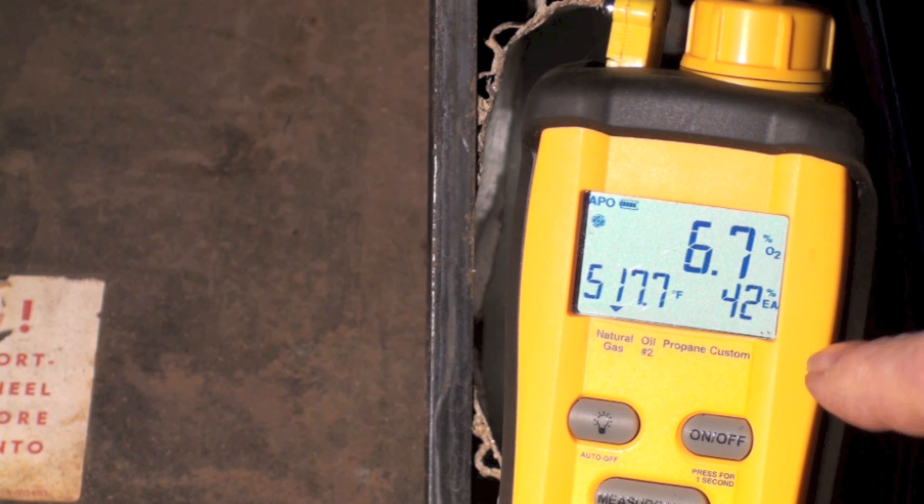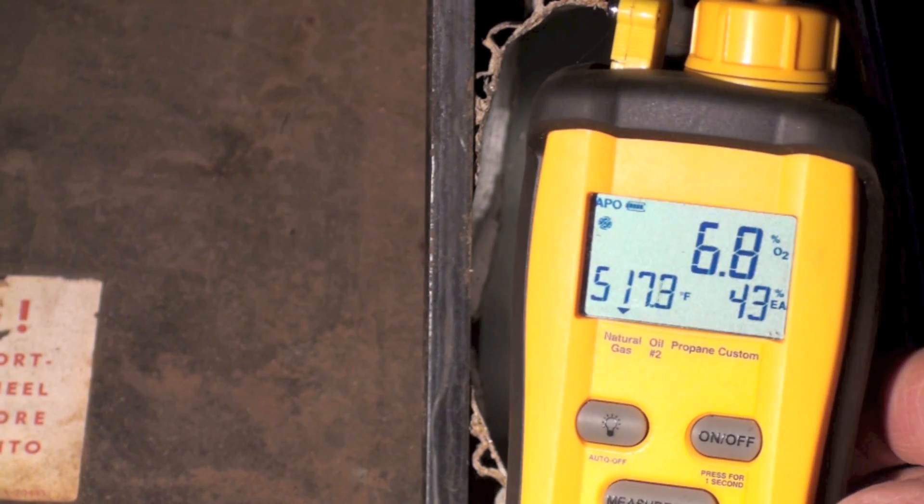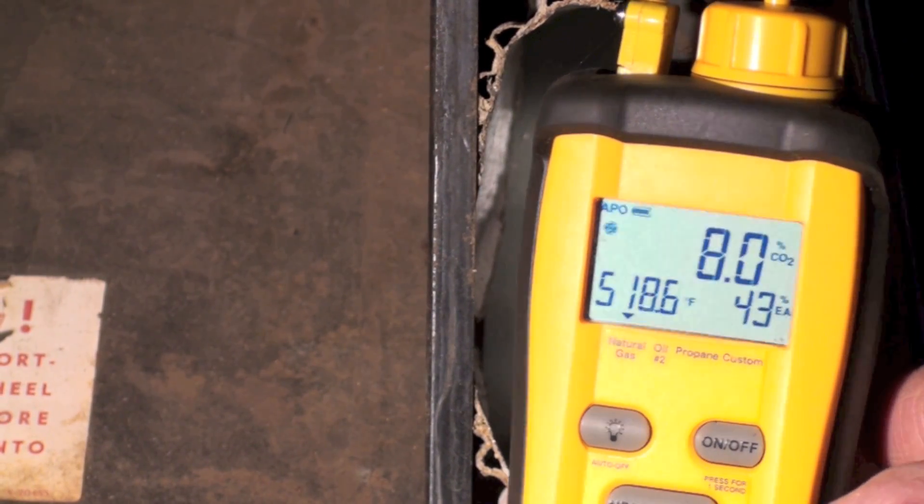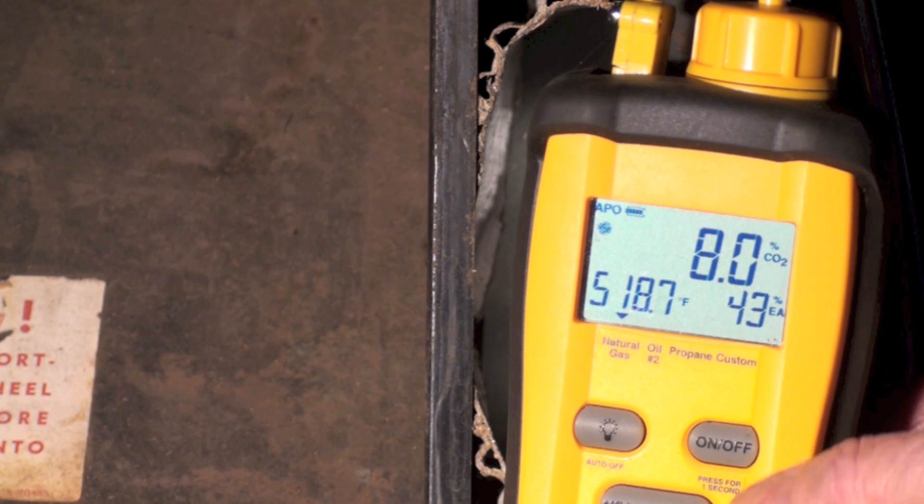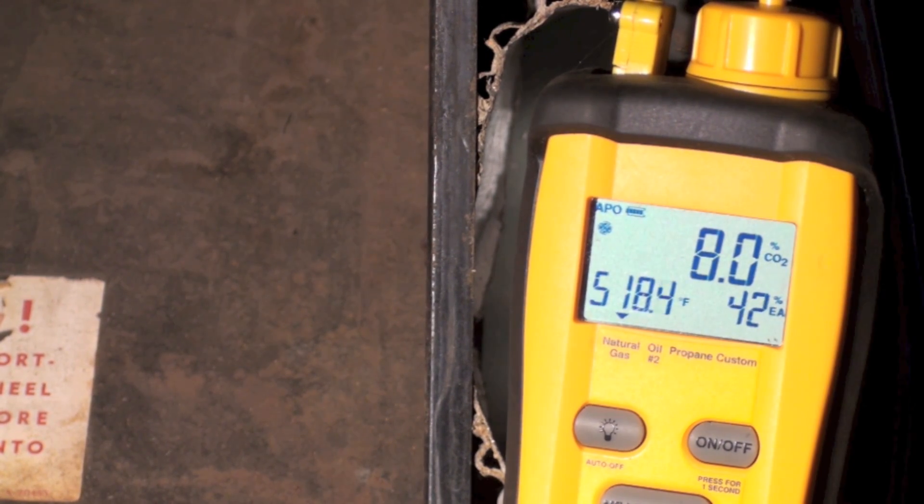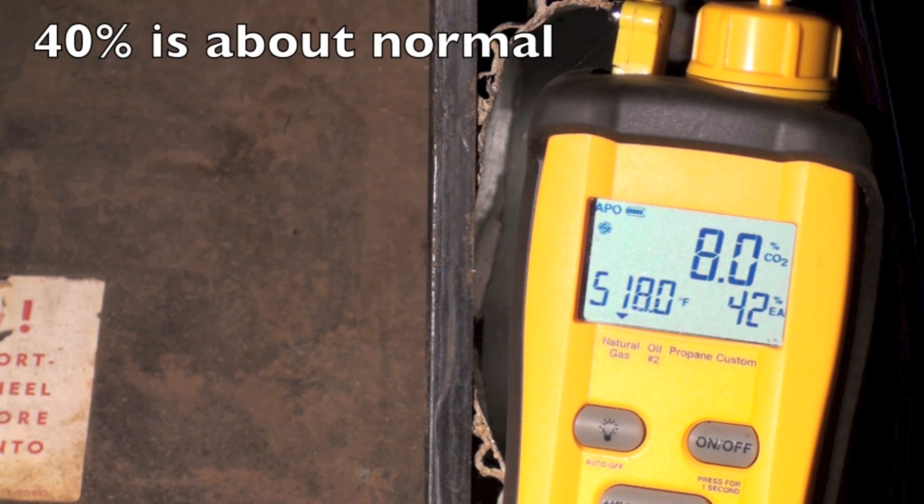Okay, go again over O2 - 6.8, CO2 - 8. Excess air is running in the low 40s. Actually, that's more like what they recommend for excess air, is in the 40s.